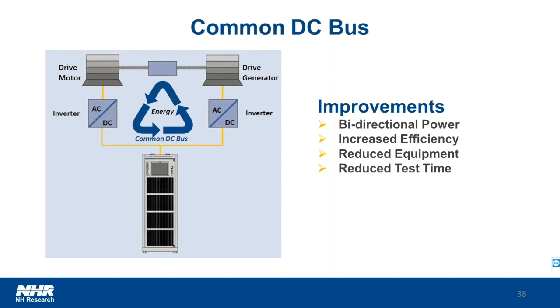With a high efficiency DC bus regulated by our battery emulator, you've now reduced the cost of testing by over 90%. This is reducing your power usage in the facility, reducing the heat in your lab, and also reducing the cost of testing. One thing to note is you do lose the ability to characterize that DC link of your test motor drive. This is because when the regen is happening, it's happening on that common DC bus, and you're feeding that current back into the inverter.